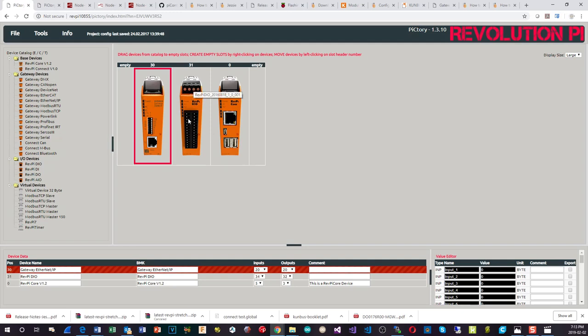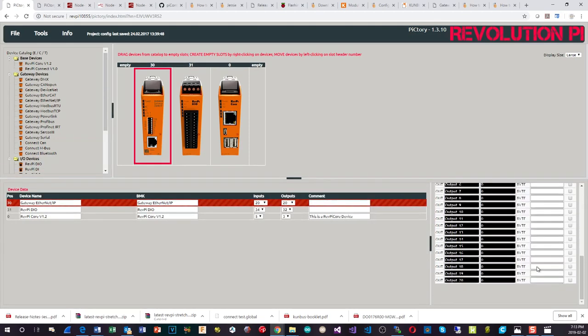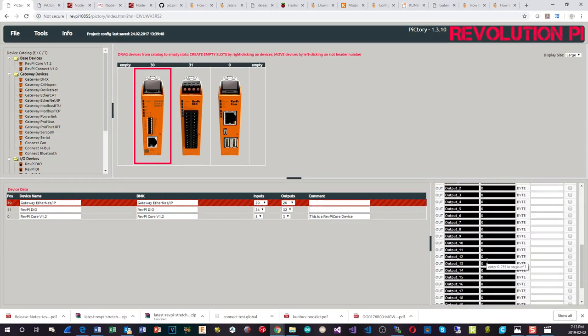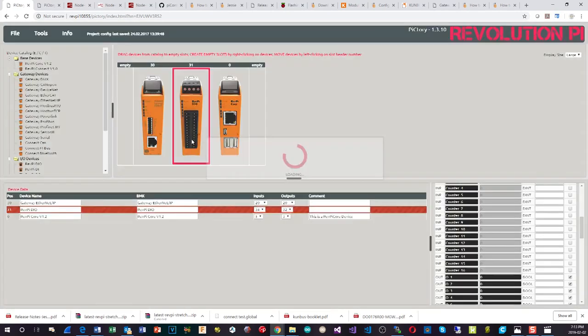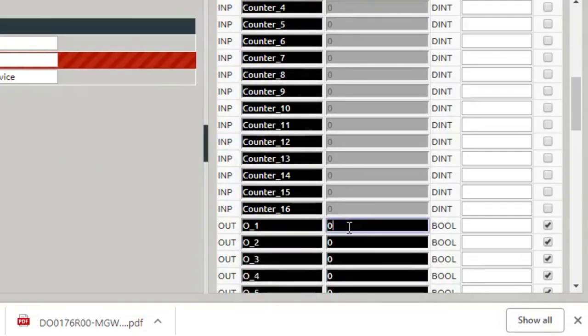On the DIO, I have a couple of relays connected on output port 0 and 1, so I could preset them to turn on by tweaking these values down in the bottom right here for the ports for that module. If I go to the DIO, sorry, you can pick which module you're configuring. So we could set these so the relays actually come on by default like that, and then that would set those outputs to be on instead of off when the unit powers up.